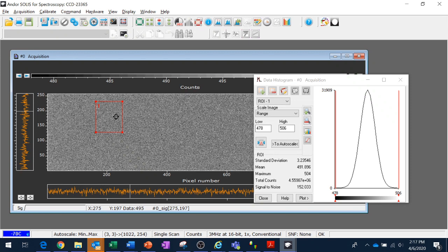So is this dark current? Is this light sneaking through? No, this is actually an offset applied at the analog to digital converter to make sure all the numbers coming out of it are above zero, which is a bookkeeping trick that makes storing numbers more efficient. So you can imagine this could cause trouble if I'm using this for some kind of photometric application, because it's going to make my background look artificially higher.